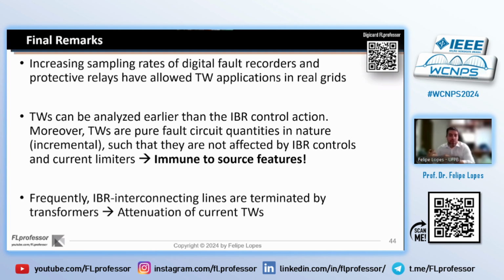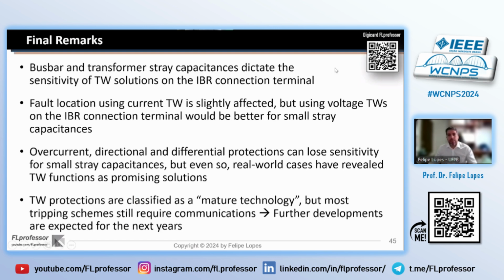Frequently, IBR interconnecting lines are terminated by transformers, as I mentioned during my presentation, and they can attenuate current traveling waves. But despite that, we could see a good operation in most of the analyzed cases. So the busbar and transformer stray capacitances will dictate the sensitivity of these functions. We could see that fault location, even using current traveling waves, is only slightly affected because it detects only the line wave travel time. But we do believe that using voltages also for fault location functions would be beneficial. And I think that in the next coming years, the manufacturers will release fault location functions that can use currents or voltages, not only one or the other.